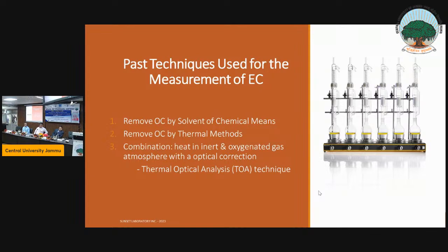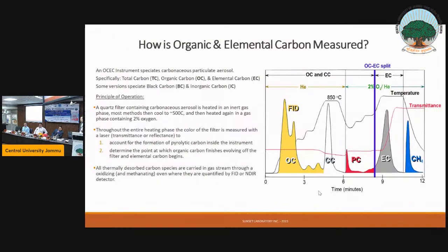And so they came up with this method called thermal optical analysis. So it's basically the same thermal analysis that I just described, but they added another component. They added a laser to monitor the transmittance through the filter. And you can actually monitor the transmittance, or you could monitor the reflectance, but you can measure them both too if you want. So here's the analysis. Here's what it looks like.